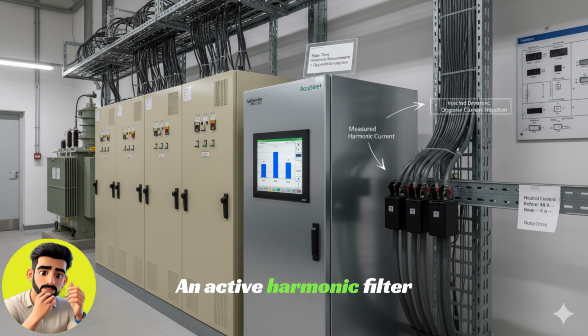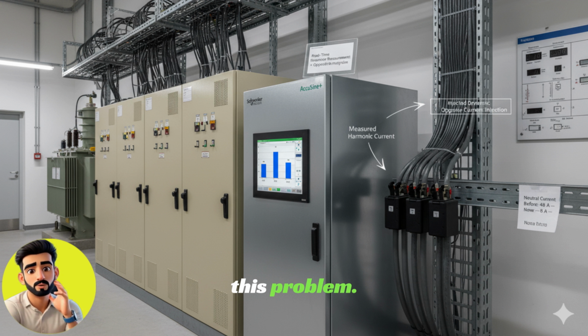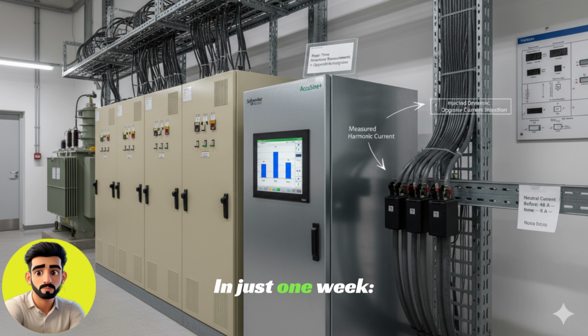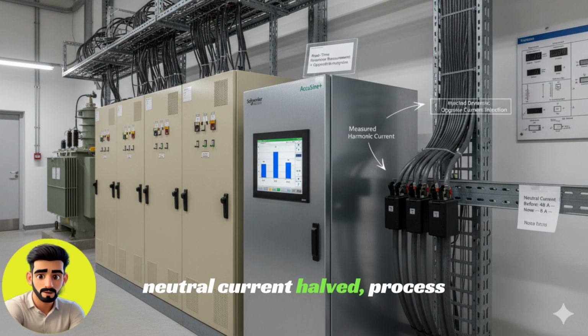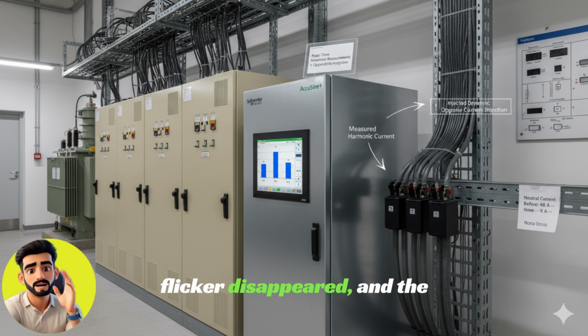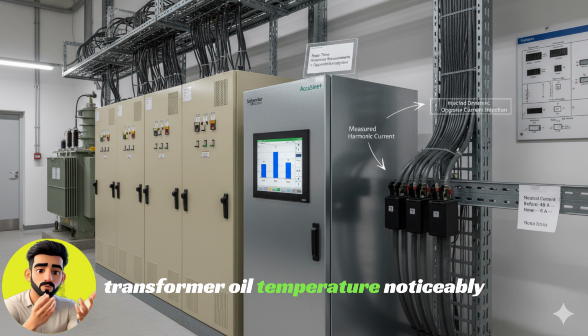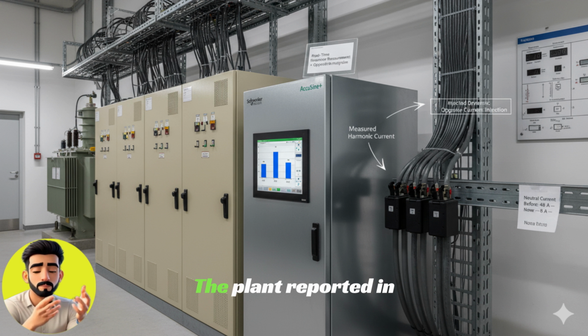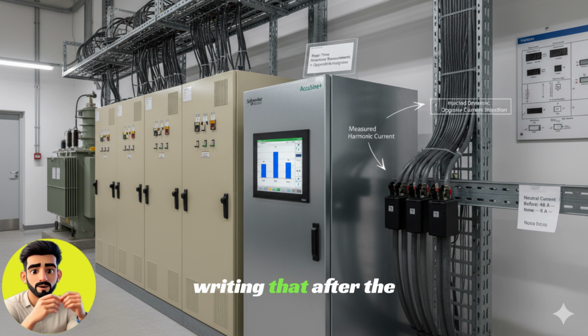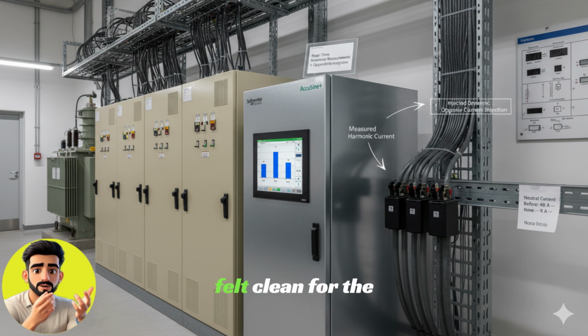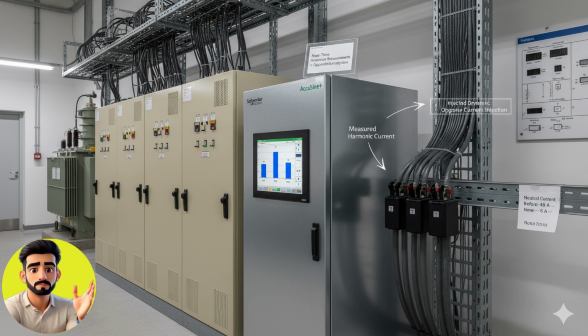An active harmonic filter was installed to solve this problem. In just 1 week, the generator stabilized, the neutral current halved, process flicker disappeared, and the transformer oil temperature noticeably decreased. The plant reported in writing that after the filter, the power quality felt clean for the first time.